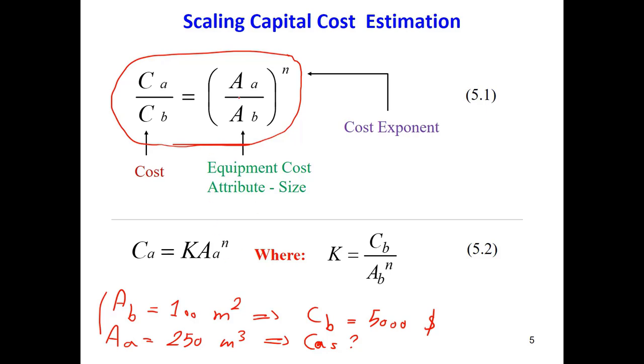The second parameter we need is 250 square meters; the first is 100 square meters. I have the previous cost — the cost for 100 square meters, which is $5,000 — and I just put it into this equation to find the cost of my heat exchanger. The most important parameter here is n, which we call the cost exponent. This cost exponent is usually approximately 0.6.